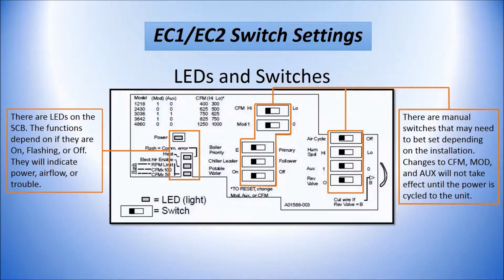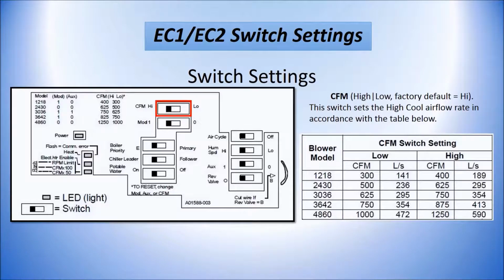This slide shows the location of the LEDs and the dip switches on the circuit board. The first switch is labeled CFM. You have two positions, high or low. Depending on what model you have is going to depend on how you set that switch. If you've got a 2430, which is a 2 to 2.5 ton, if it's a 2 ton, you're going to set that switch on low for the proper airflow. If it's a 2.5 ton, you're going to set it on high. If you look at the table to the right, for a 2430, if it's a 2 ton, we need 500 CFM. If it's 2.5 ton, we need 625 CFM. This setting is going to allow it to ramp up to the proper speed.